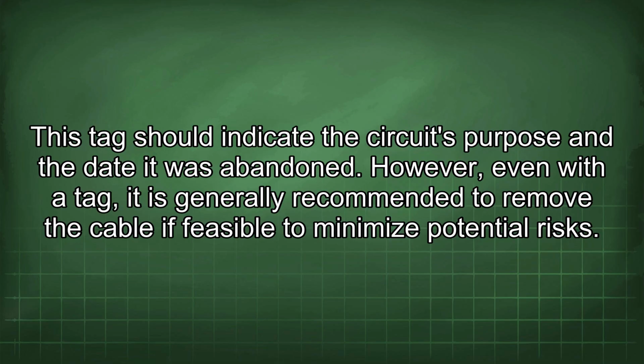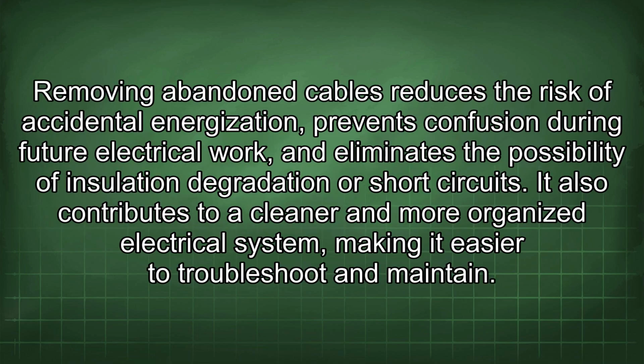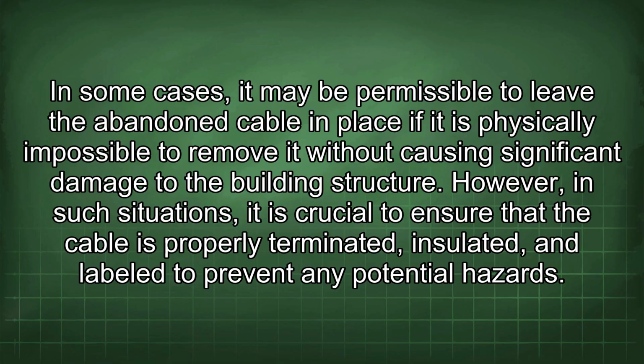However, even with a tag, it is generally recommended to remove the cable if feasible to minimize potential risks. Removing abandoned cables reduces the risk of accidental energization, prevents confusion during future electrical work, and eliminates the possibility of insulation degradation or short circuits. It also contributes to a cleaner and more organized electrical system, making it easier to troubleshoot and maintain. In some cases, it may be permissible to leave the abandoned cable in place if it is physically impossible to remove it without causing significant damage to the building structure.